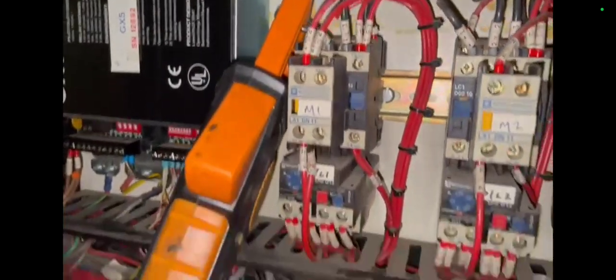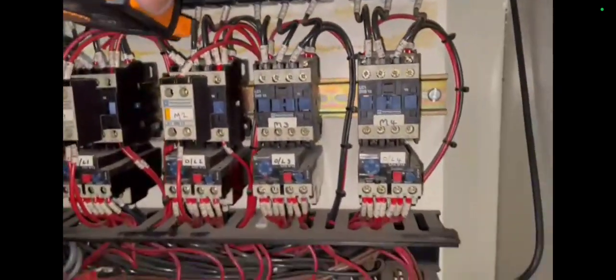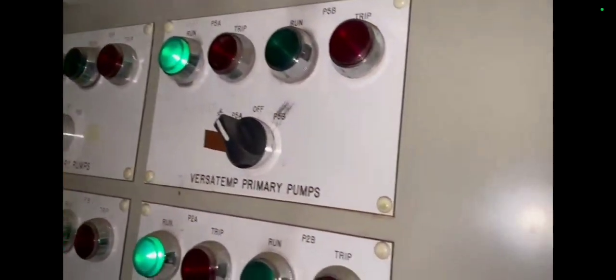So now going back to pump two, which was our bottom pump, which it was switched to. And what do we have on that phase? So pump two, phase two. That's 1.16, so good reading there.